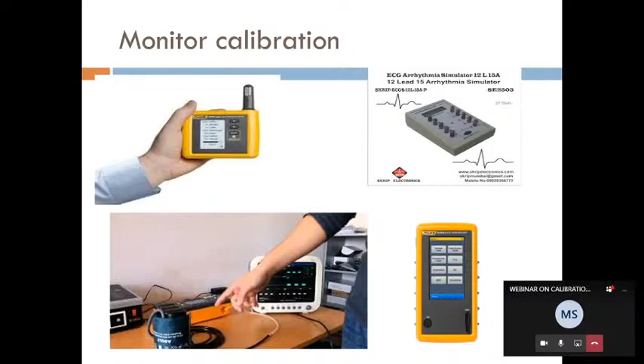How do you calibrate NIBP? NIBP is non-invasive measurement of blood pressure. Instead of connecting the cuff to the patient, you connect the cuff to something like a patient hand, and connect the output tube to this analyzer. The same value has to be observed in the monitor. For example, if you set 120/80 pressure in the analyzer, the same thing has to be observed in the monitor. With this analyzer, you can test a hypertensive adult and a hypotensive adult. Whatever value you set in the analyzer, the same value has to be observed in the monitor. This is the principle by which you can calibrate the monitor.